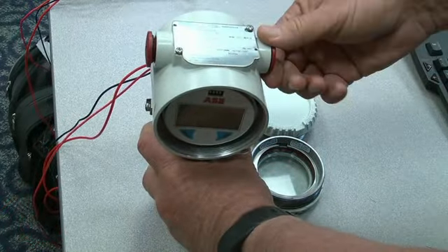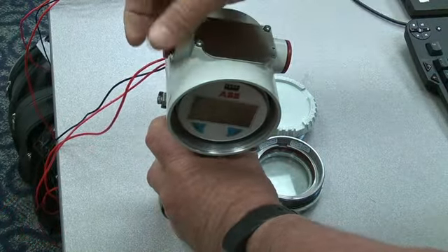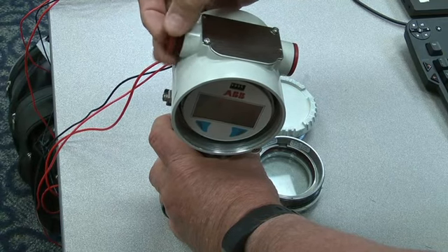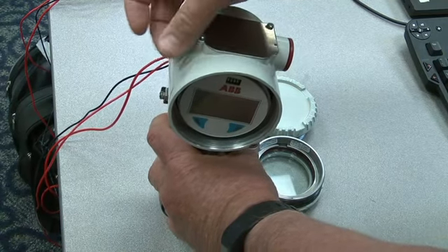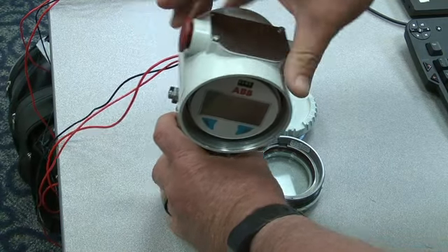These two plugs are standard from the factory, and they're not waterproof, and they're not designed to keep water out. So we want to make sure that if you do an installation in the field that these are replaced with steel, and they need to be sealed. There's two ground lugs, one on the outside of the case and then one on the inside of the case, and these do need to be grounded to solid ground.